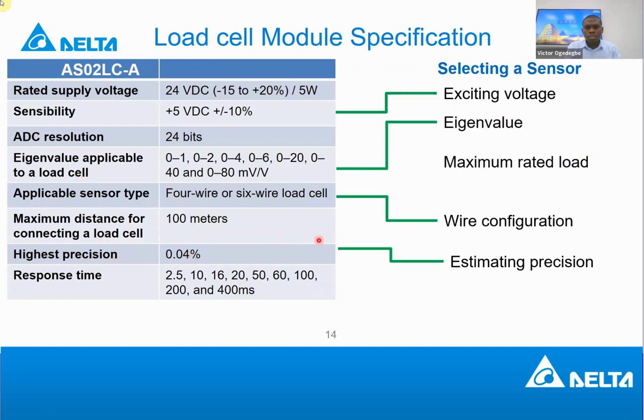Precision could differ. Another thing that's also important again is the measuring time, which is closely related to the precision. When you are measuring your application, it is good, if possible, to choose a bigger response time. This response time is the time it will take for the load cell module to sample the analog signal coming from the sensor. When the time is big, it makes what is being measured balanced. So the bigger the time, the more stable the measurement and the less interference you will have in the measurement.